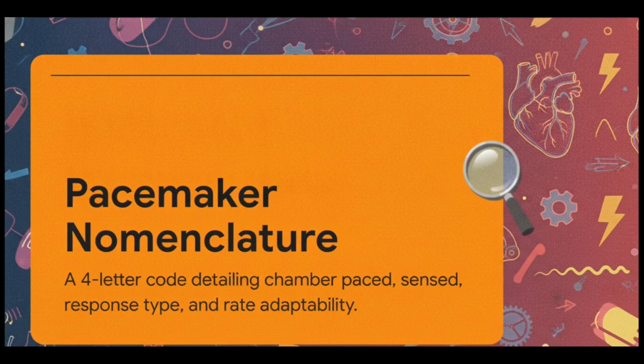Clinicians use this alphabet soup to instantly communicate exactly how the device is interacting with a patient's unique physiology. The first letter tells you where the spark is actually delivered, the chamber paced. The second letter tells you where the pacemaker is listening, the chamber sensed. The third letter dictates the device's response. Does it inhibit its own spark if it hears a natural beat, or does it trigger one?